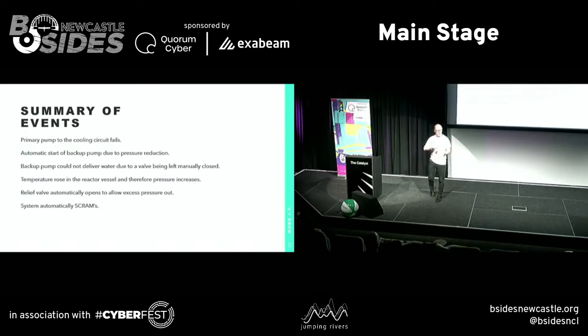The water that's stuck in that loop is getting hotter and hotter with the reaction in there. Okay, no problems. Second safety thing happens. The temperature's risen, the pressure's gone up because the water's getting hotter and hotter. The relief valve opens so that it doesn't get too high pressure. No problems. Poof. Relief valve goes, starts to dump out some of the pressure into the relief tank. Because that's opened, the reactor now goes, I'm in an unsafe state, I'm going to scram.